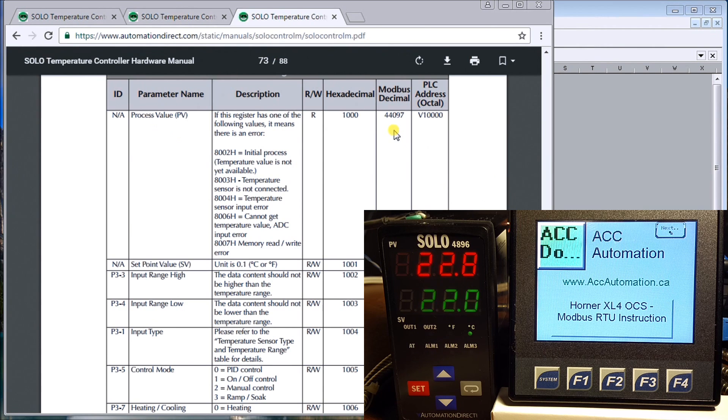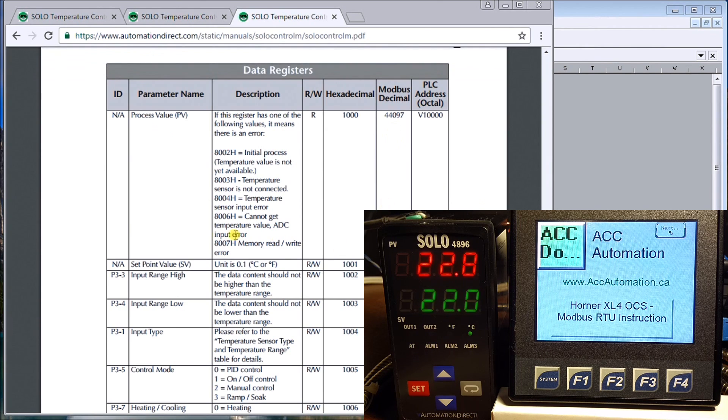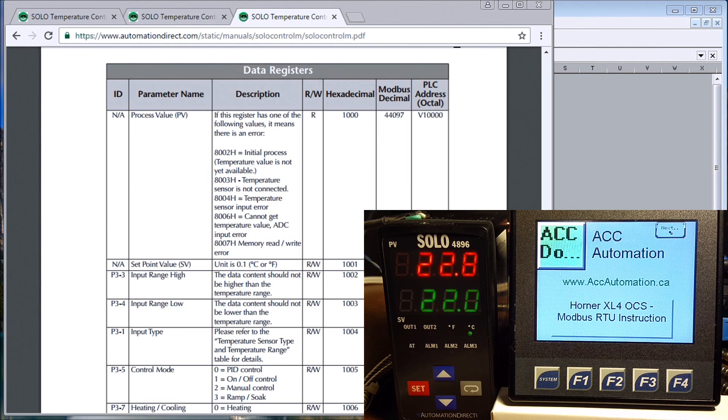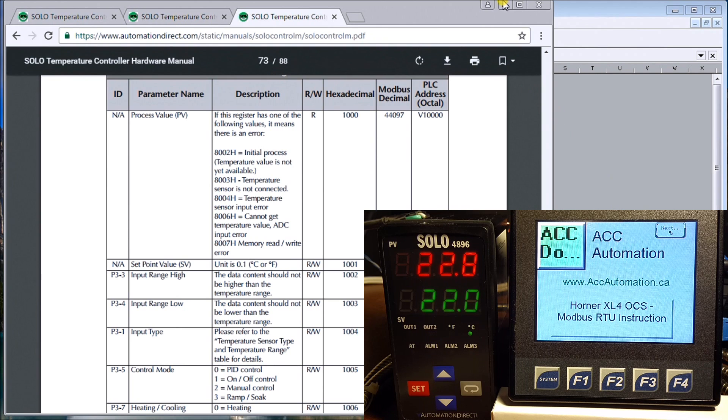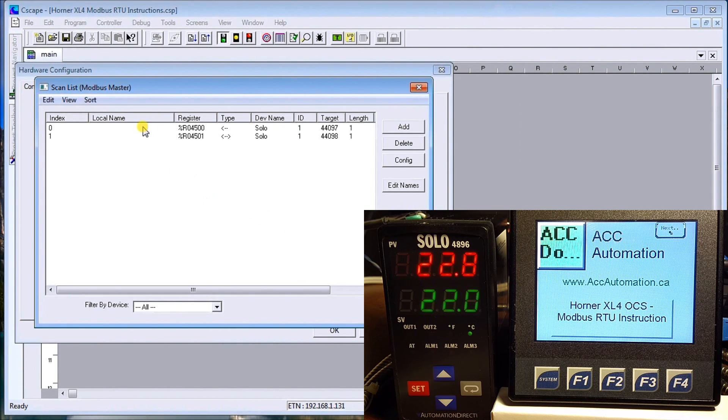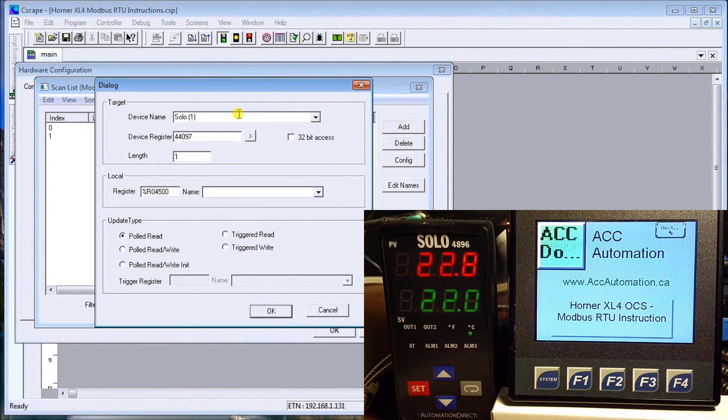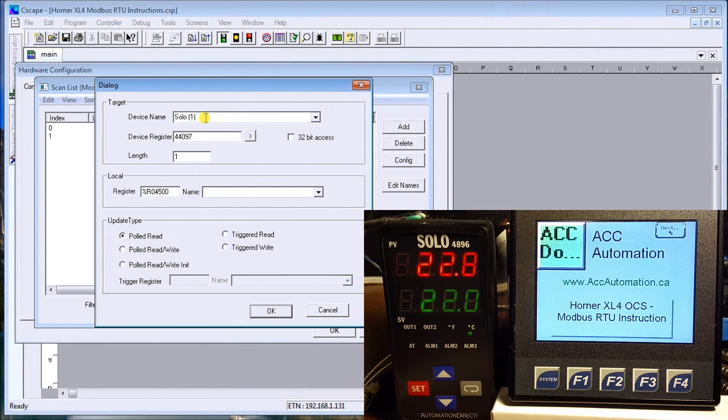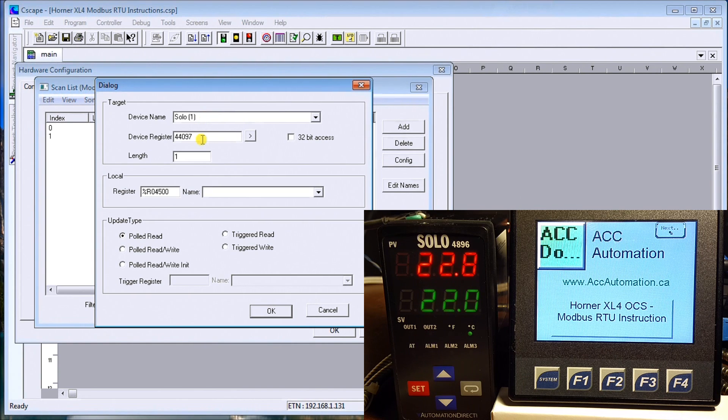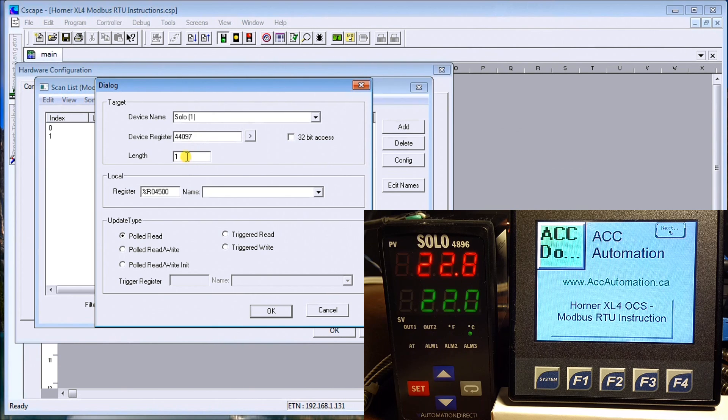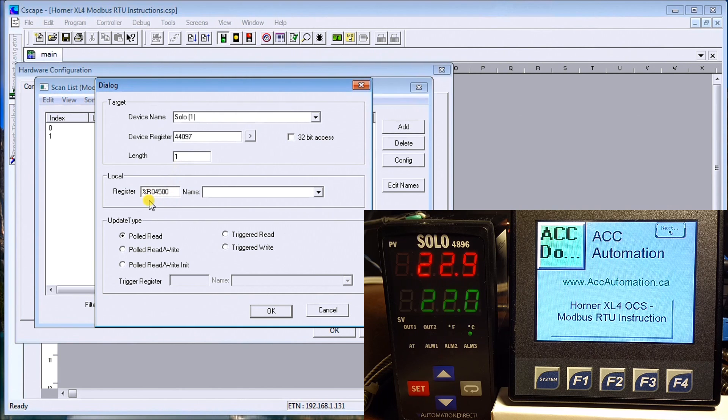My set value, which is a read and write, is 44098. Those are my addresses I'm looking for. Looking on this one, this is my present value. If we go into the configure here, you see SOLO 1 is our device. We look at 44097, which was exactly that same address. It's one word in length, so 16 bits.